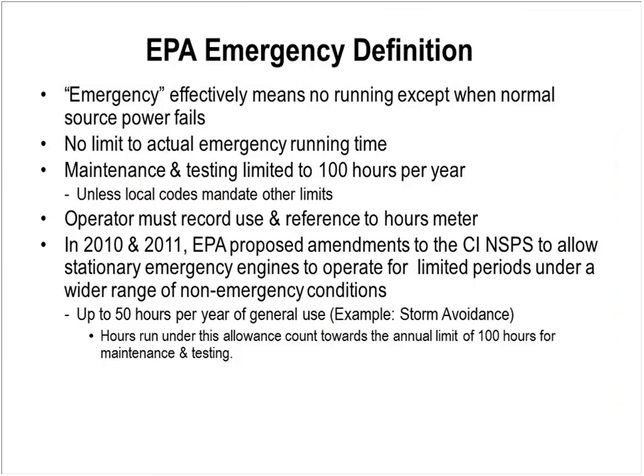There have been a number of adjustments to this definition of emergency, as the EPA listened to industry and operators and tried to make it more flexible. In 2010 and 2011, they proposed an allowance of some 50 hours a year, as part of the 100 hours, to cover non-emergency operation for circumstances such as storm avoidance—for example, running a data center on generators if severe weather is approaching.